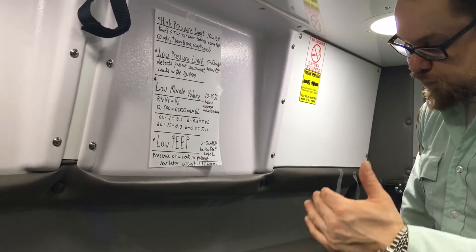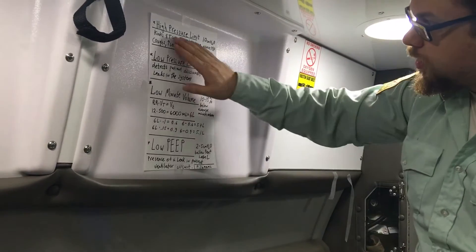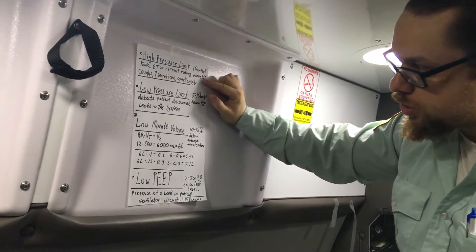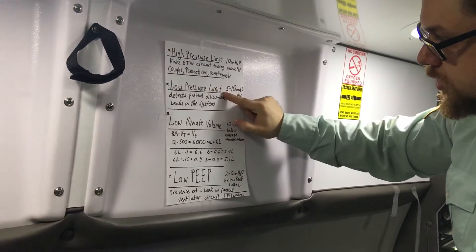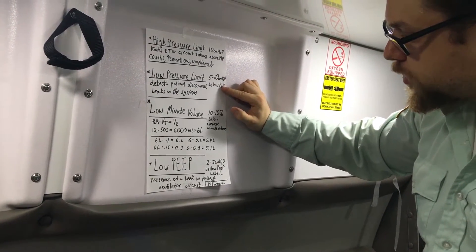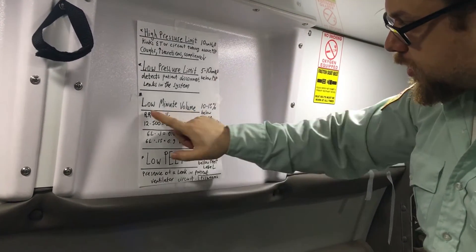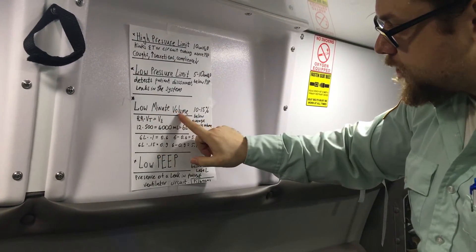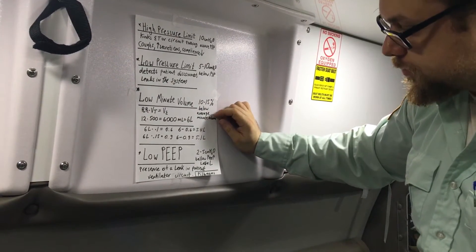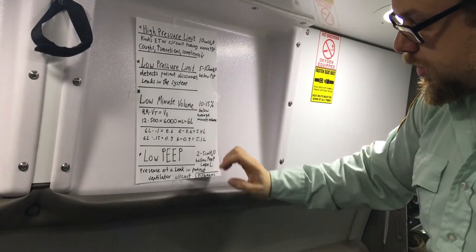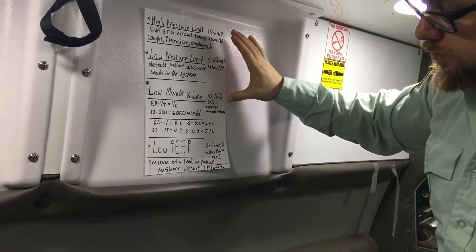So just to review all of them: high pressure limit is 10 above peak inspiratory pressure. Low pressure limit is 5 to 10 below peak inspiratory pressure. Low minute volume is 10 to 15% below your minute volume. These are the limits that we're actually inputting.